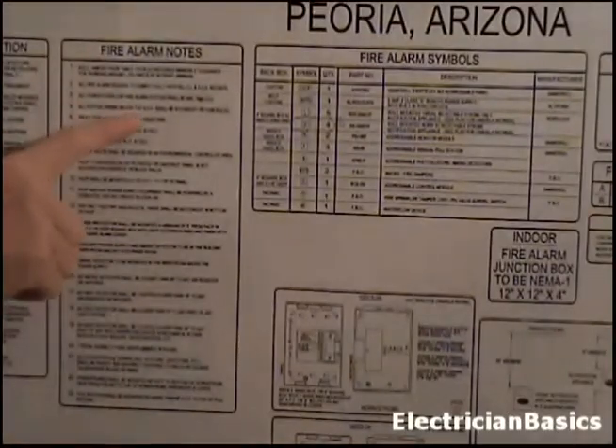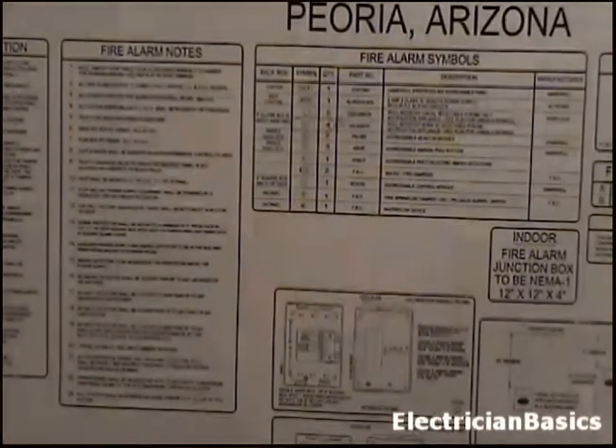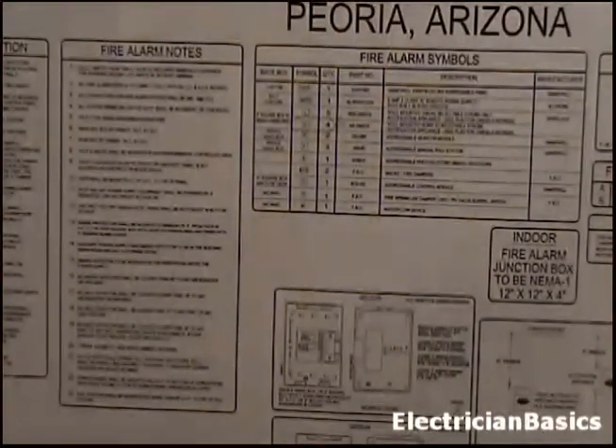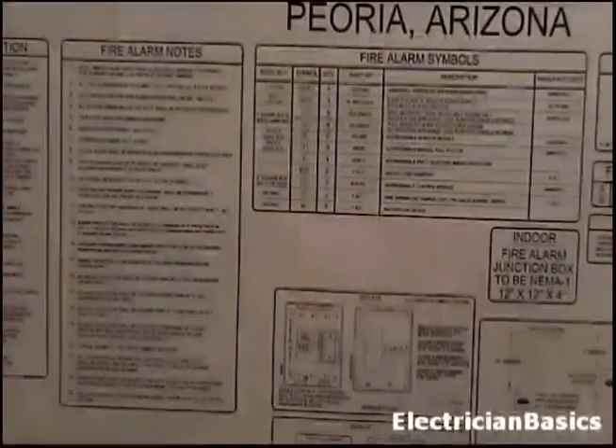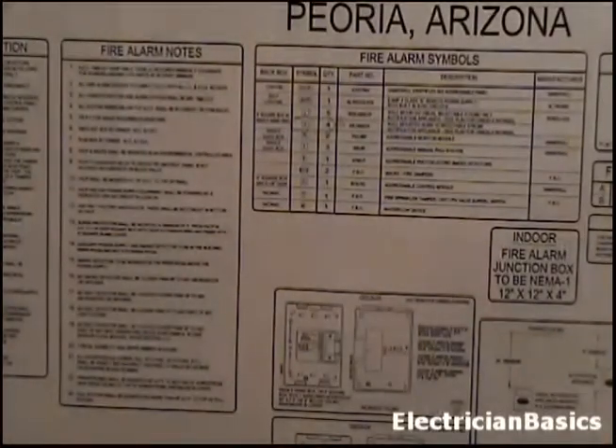It says all system wiring below 7 feet above finished floor shall be in conduit or concealed. 7 feet is 7 times 12 inches, and that's 84 inches. Now we earlier spoke of some other devices mounted at 80 inches above finished floor. So we're right in that range of overlapping. They're saying at 84 inches, anything below that has to be in conduit. Now again, we mentioned not all fire alarm systems require the entire cabling to be in conduit. Some do. But they're saying anything below 7 feet above finished floor has to be in conduit or concealed. And concealed could be within a junction box, of course, which is a conduit body.